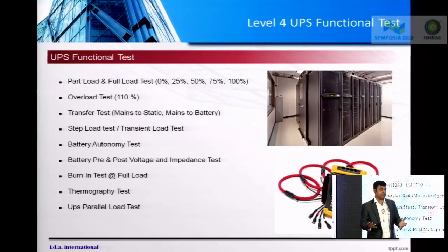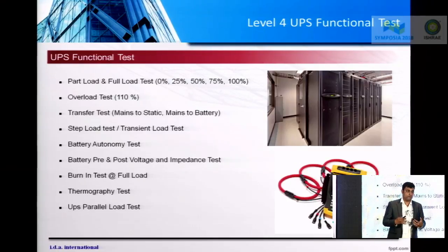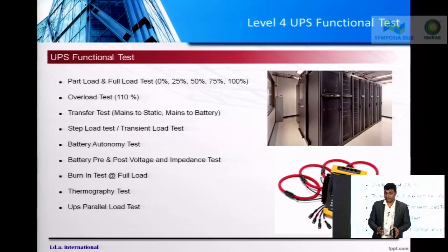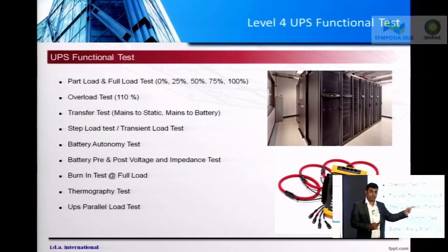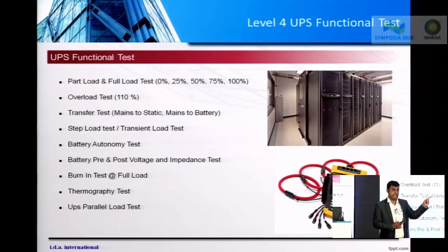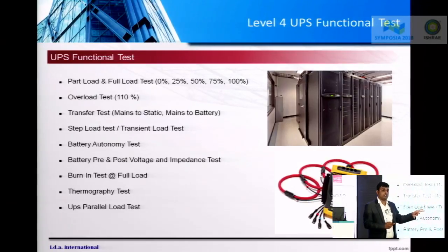The second point is overload test. All the OEMs claim that their equipment can handle overload for a certain duration. So it has to be verified, right? So we will verify a UPS for 110% of its capacity. The third is transfer test.